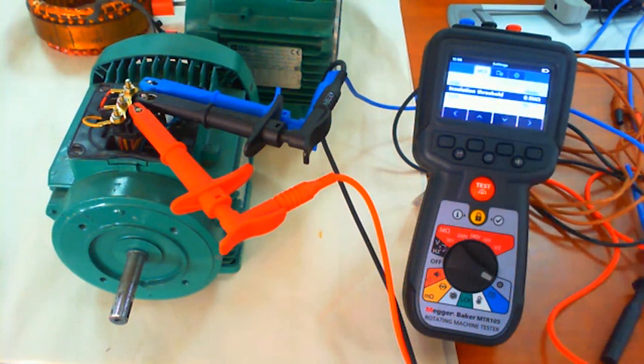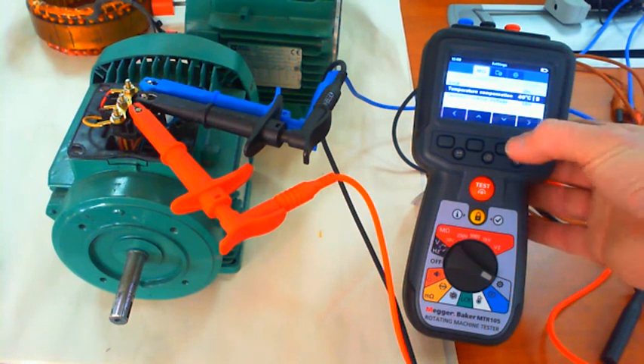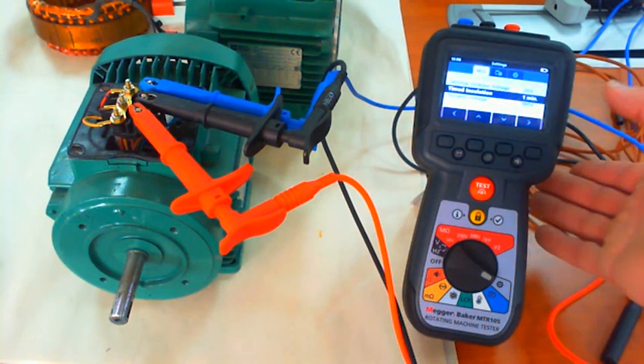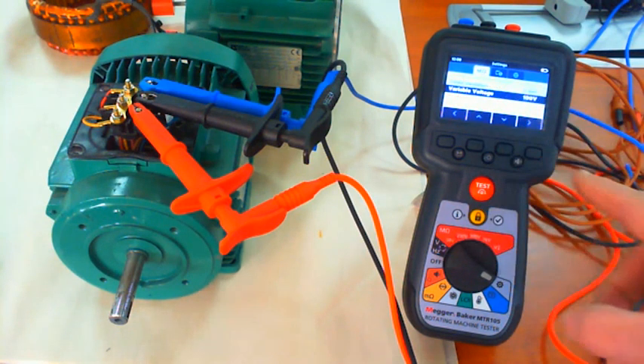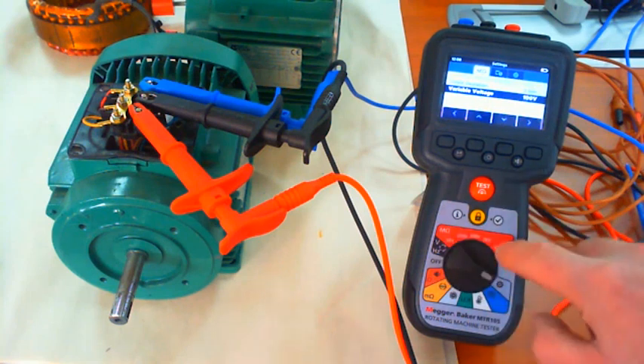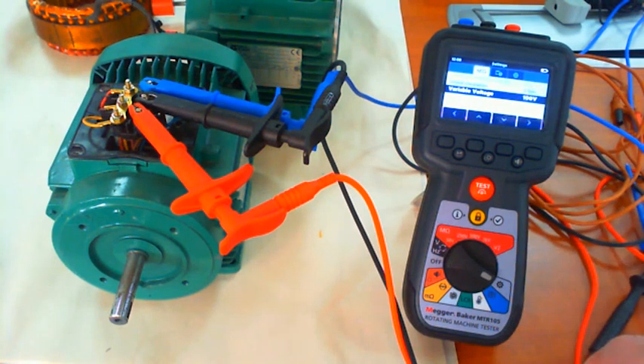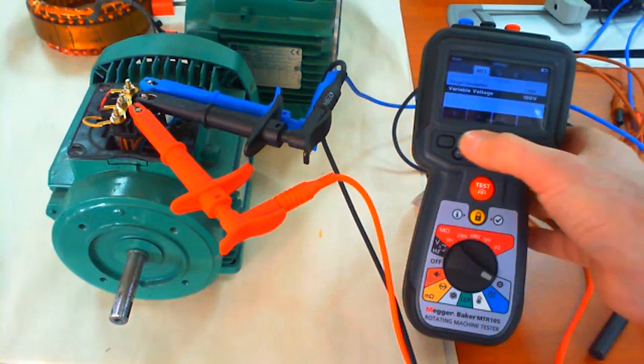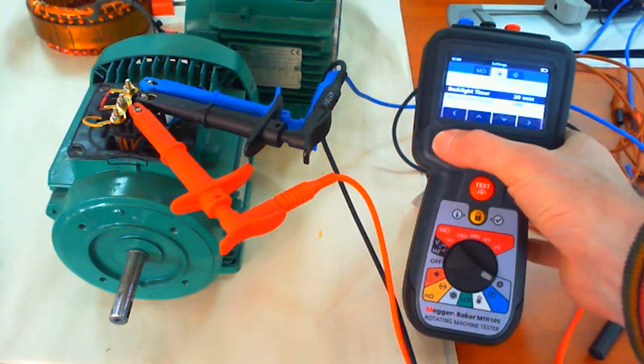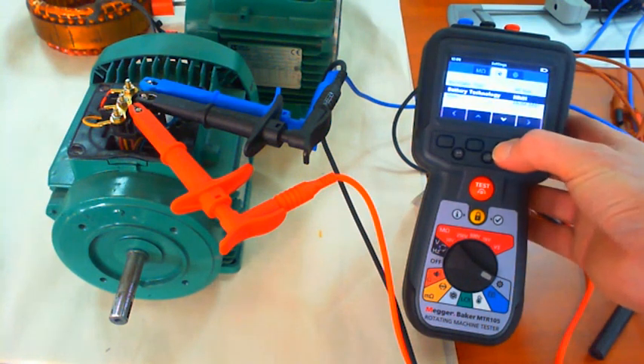We can look at the insulation threshold. So when we do an IR test, if the IR value is below a certain level, we'll get an indication. Temperature correction. How long is the timed insulation test? And for the variable voltage setting, if I go to this setting here, I can actually set a specific voltage to test at. Any voltage between 10 and 1000 volts for the IR test, but I can only change by 10 volt increments. Language, backlight, type of batteries, and so on.